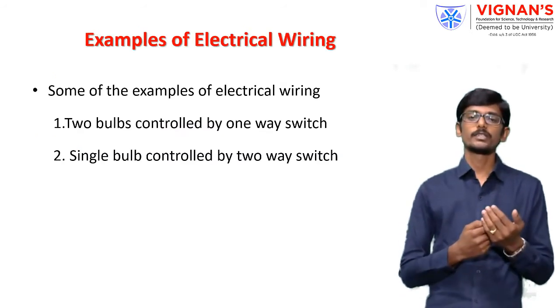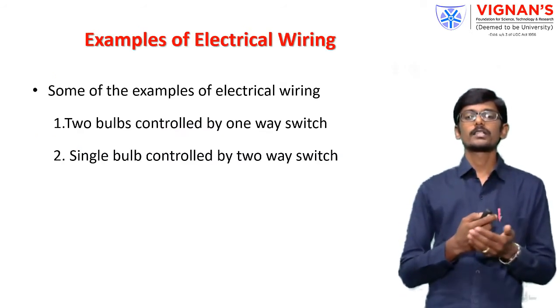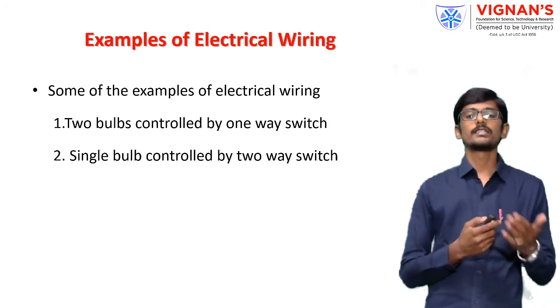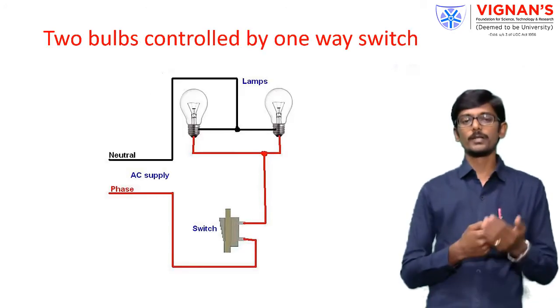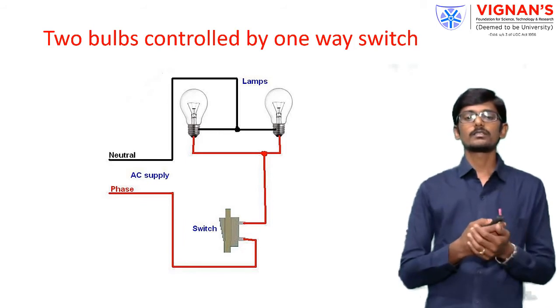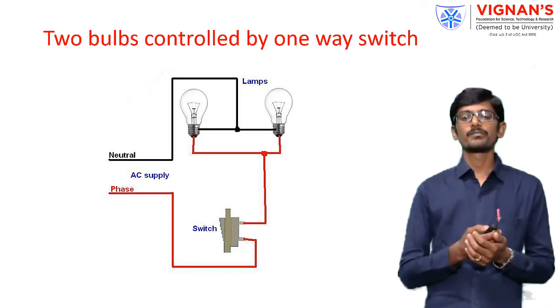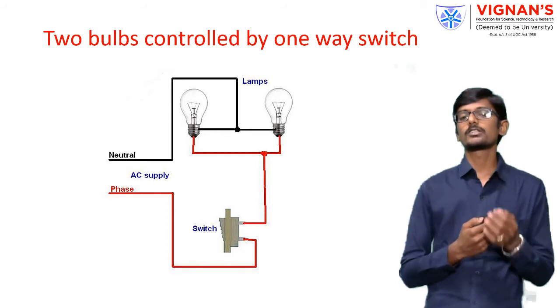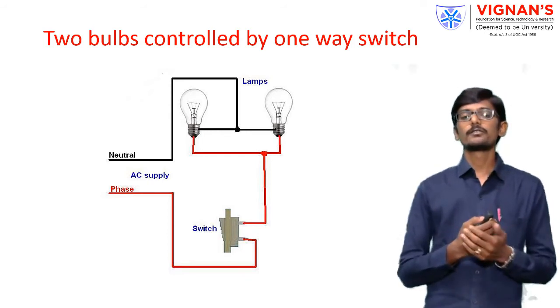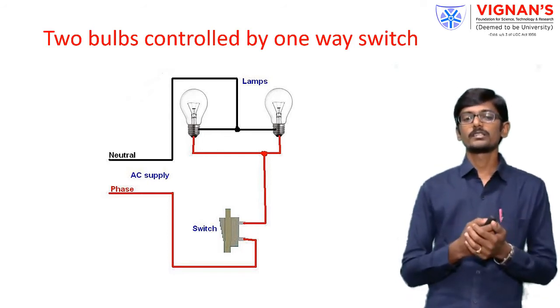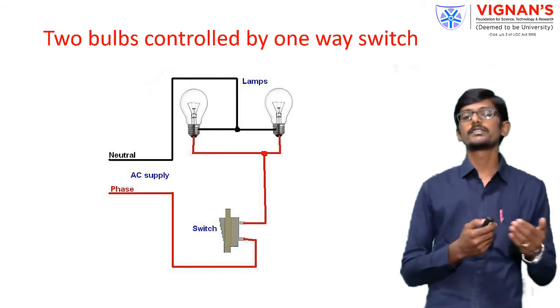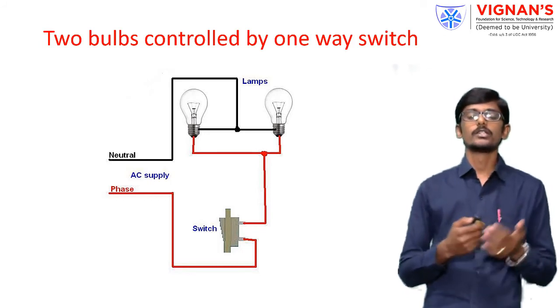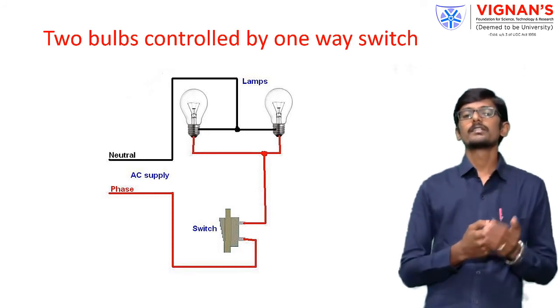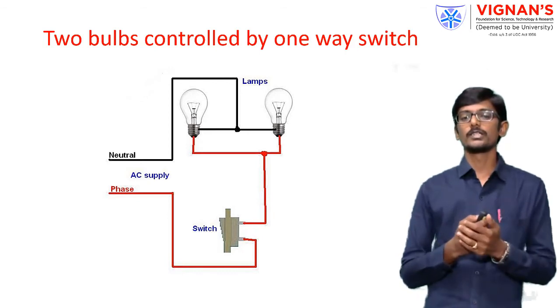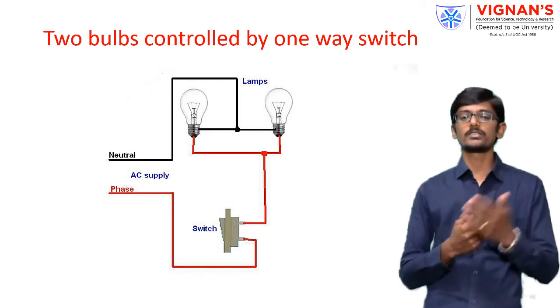Examples of electrical wiring are 2 bulbs controlled by a one-way switch and a single bulb controlled by two-way switches. Two bulbs controlled by a one-way switch shows that the phase connection is given to the switch. Remember that the phase should be connected to the switch only. Otherwise, if we connect the neutral connection to the switch, the neutral will be controlled, but the phase directly enters the lamp. If we touch the lamp, there may be a risk of electrical shock. So, in every wiring system, the phase should be connected to the switches only. The neutral will be directly connected to the other points of the bulb.